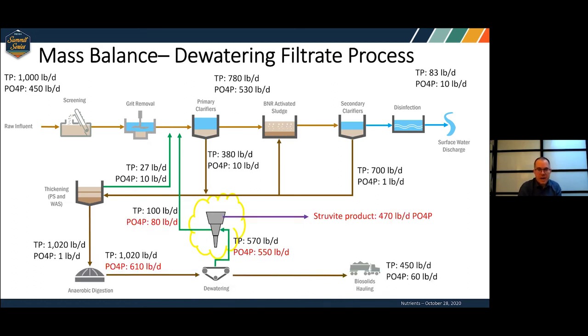Now we've moved the recovery system to the filtrate stream. What you'll notice is the dewatering system is now getting a phosphate load — about 600 pounds of PO4-P — so there is a higher struvite risk compared to the digested sludge treatment option. But this system has many of the same benefits: you're producing a lot of struvite, removing that feedback loop, with relatively low secondary influent levels and similar digester numbers. The big difference is just whether you place the system before or after dewatering.